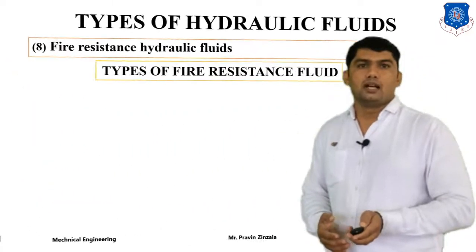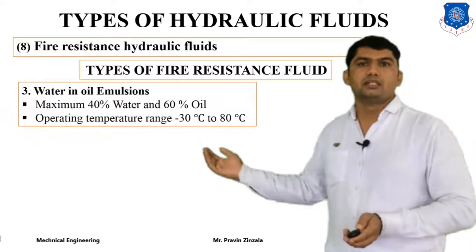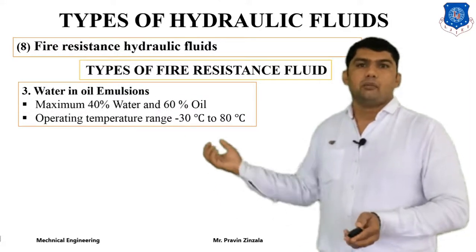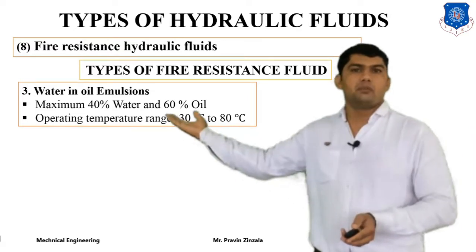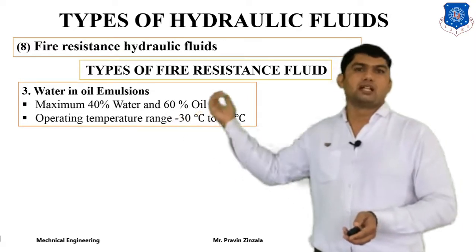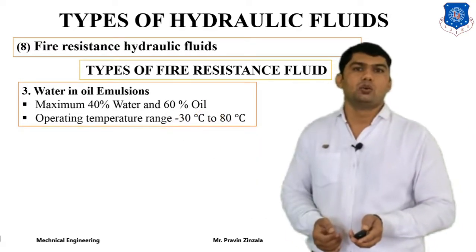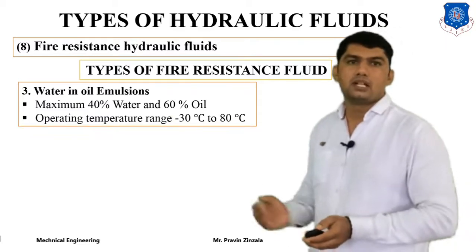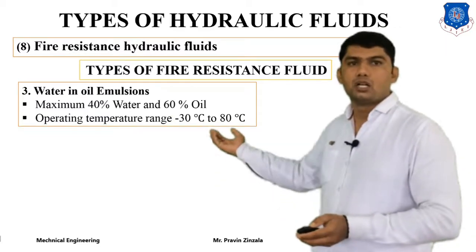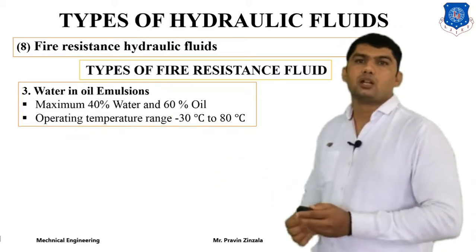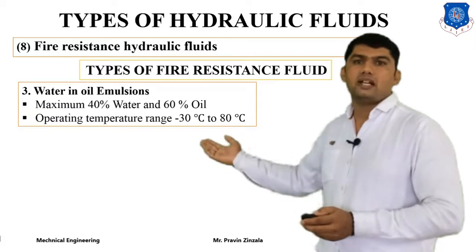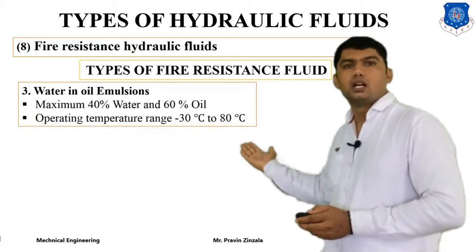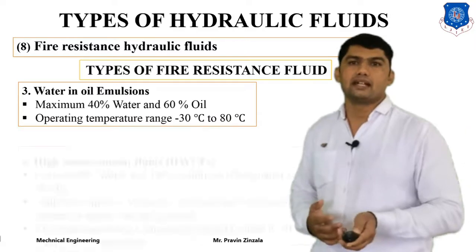The third fire resistance fluid is water in oil emulsion, with a maximum of 40% water and 60% oil. It has higher lubricant properties compared to water glycol solution, and its operating temperature is minus 30 degrees centigrade to 80 degrees centigrade.